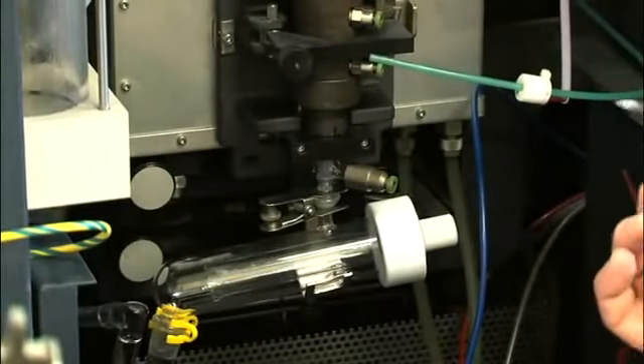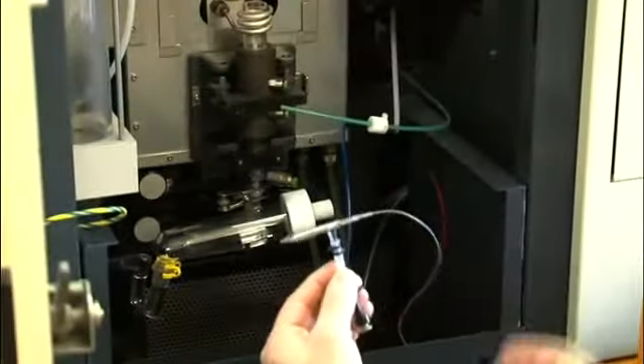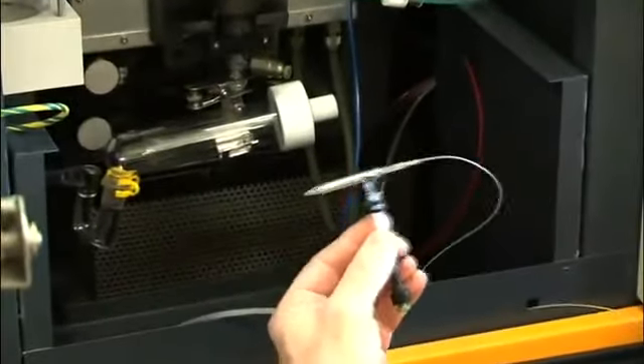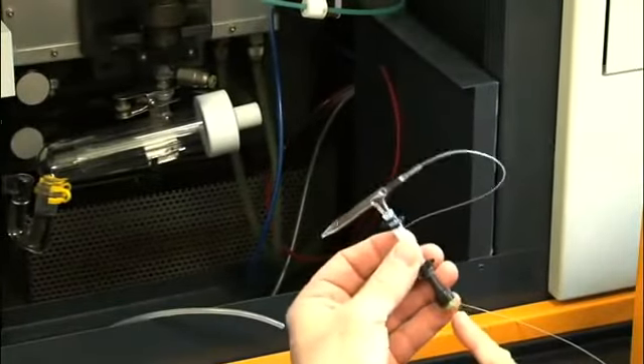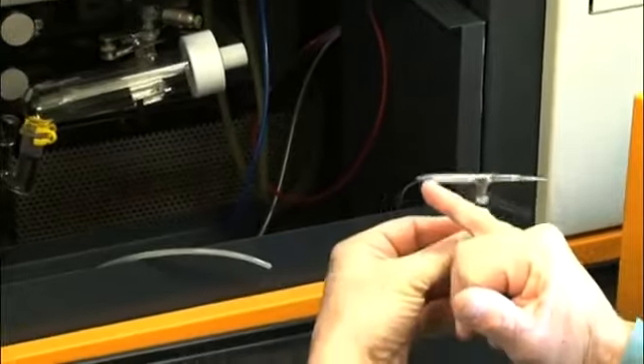This is your nebulizer. Your sample, your liquid, will come in here from the pump. Your argon gas will come in here. The two mix and you get a mist which fills the entire spray chamber.